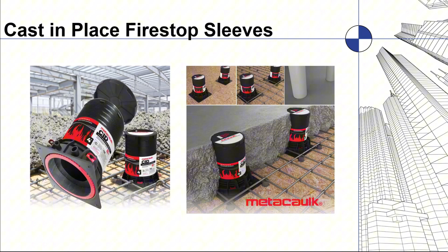Electrical boxes are also considered a penetration, but they're a bit different from the through penetrations we've looked at so far, where a pipe goes through both sides of a wall. Electrical boxes typically only go through one side of the wall. You might have back-to-back boxes so they line up, but generally these are called membrane penetrations, since they only penetrate one side of the membrane of the fire-rated construction.